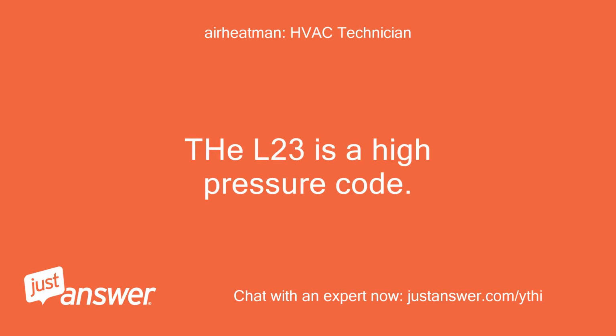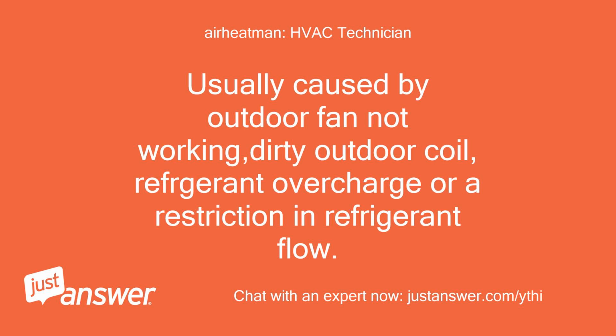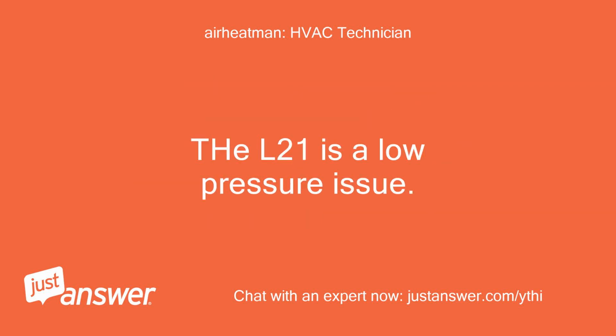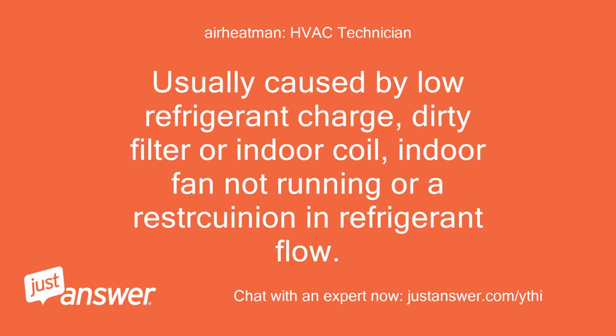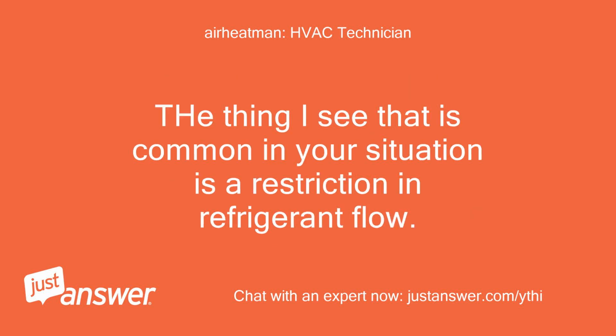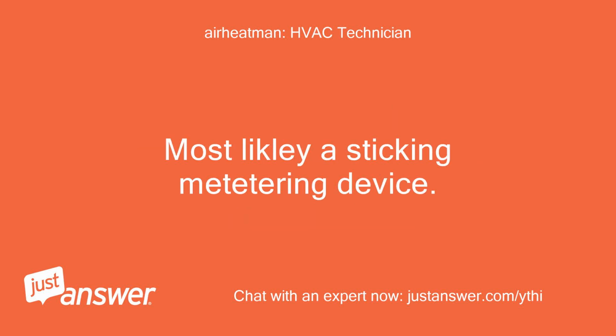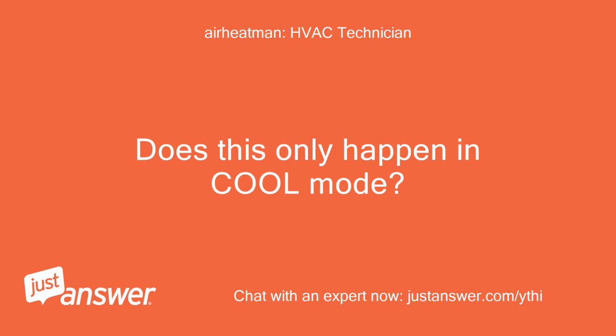The L23 is a high-pressure code. Usually caused by outdoor fan not working, dirty outdoor coil, refrigerant overcharge or a restriction in refrigerant flow. The L21 is a low-pressure issue. Usually caused by low refrigerant charge, dirty filter or indoor coil, indoor fan not running or a restriction in refrigerant flow. The thing I see that is common in your situation is a restriction in refrigerant flow. Most likely a sticking metering device. Does this only happen in cool mode?